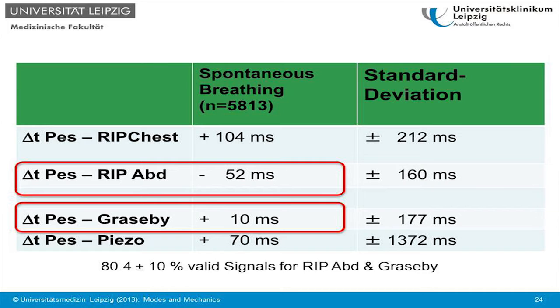Here are the time delays between the esophageal pressure and the RIP band, and this is 52 milliseconds and 10 milliseconds. These are pretty low values, and RIP band on the abdomen seems to work better than the RIP band attached to the chest, which is logical because when the baby inspires, the abdomen will rise every time, but the chest may not rise because the baby may have retractions, and actually the chest may lower, and then the RIP band will not get as good a signal as if placed on the abdomen. So the abdomen seems to be a good place to determine infant breath.